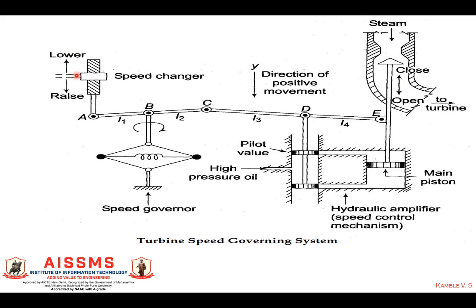Similarly, if we move the speed changer in the upper side — that is, in the upward direction — A moves upward, B downward, C upward, D downward. When D moves downward, the high-pressure oil moves in that direction and the piston moves in the upward direction. Due to this upward movement, the steam valve moves toward closure — that is, the rate of flow of steam is decreased. Due to the decrease in steam flow, the turbine speed decreases, and due to the decrease in turbine speed, the generator rotates at a lower speed — that is, frequency and active power are decreased.